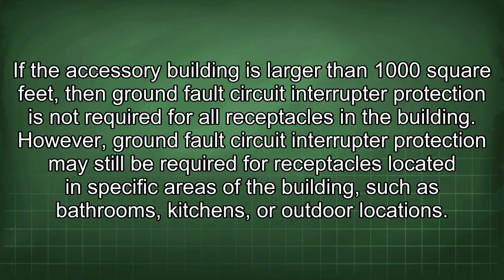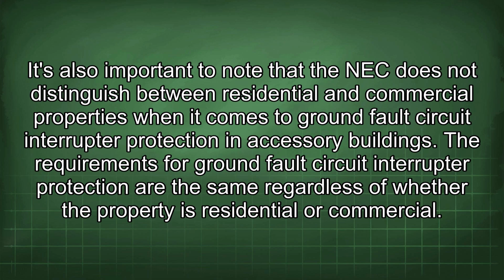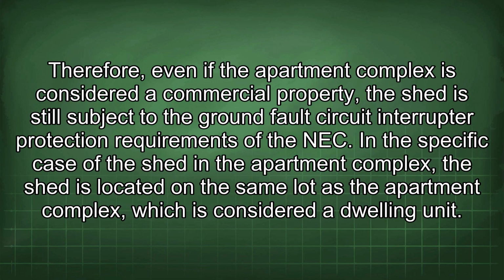However, ground fault circuit interrupter protection may still be required for receptacles located in specific areas of the building, such as bathrooms, kitchens, or outdoor locations. It's also important to note that the NEC does not distinguish between residential and commercial properties when it comes to ground fault circuit interrupter protection in accessory buildings. The requirements are the same regardless of whether the property is residential or commercial. Therefore, even if the apartment complex is considered a commercial property, the shed is still subject to the ground fault circuit interrupter protection requirements of the NEC.